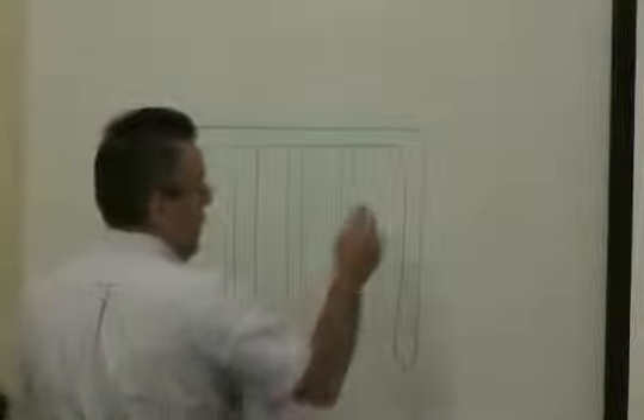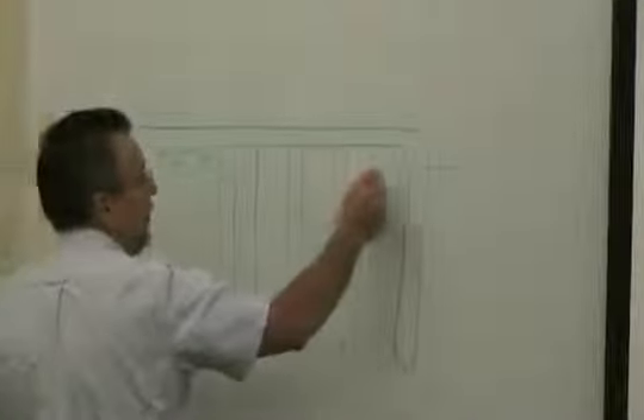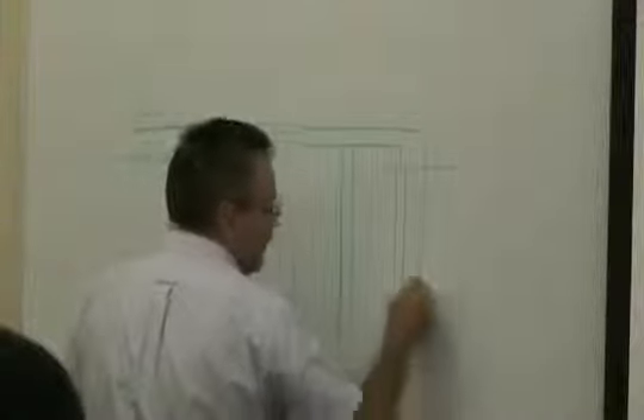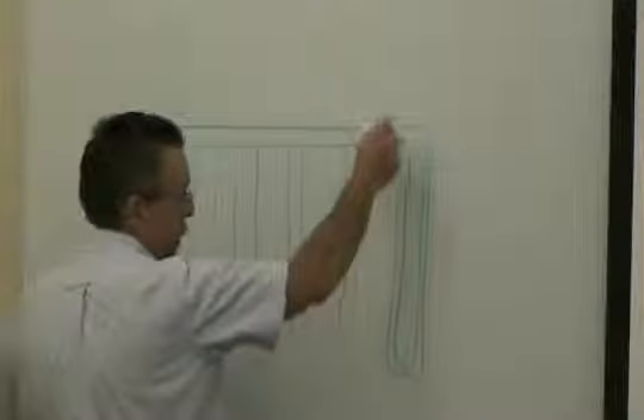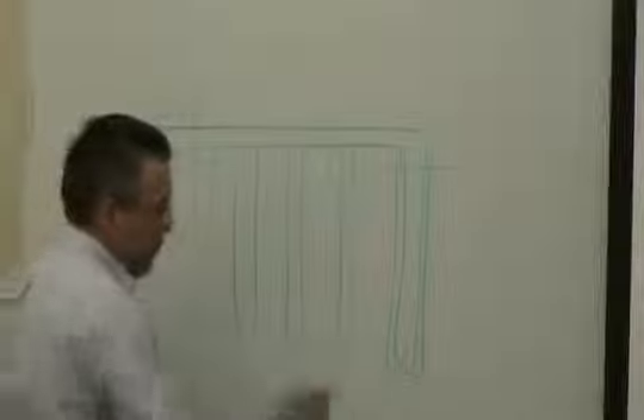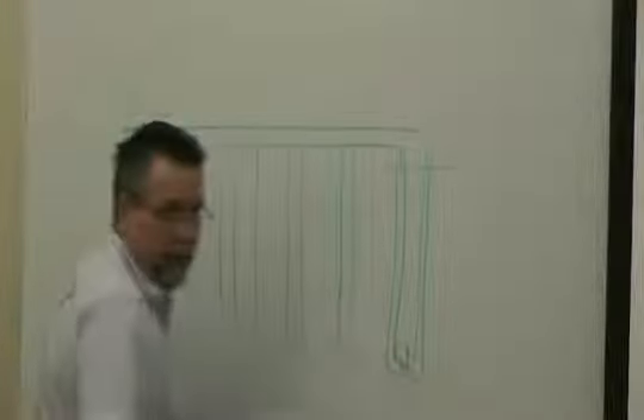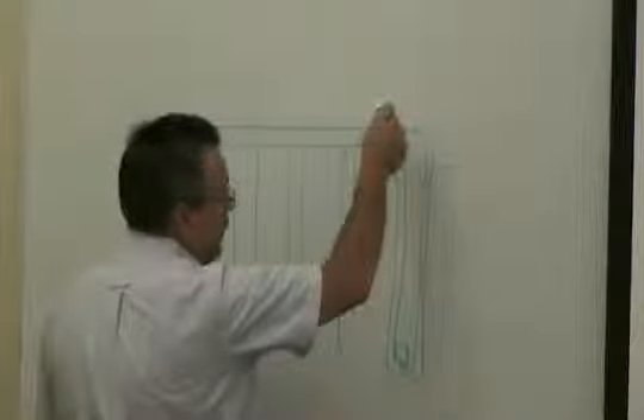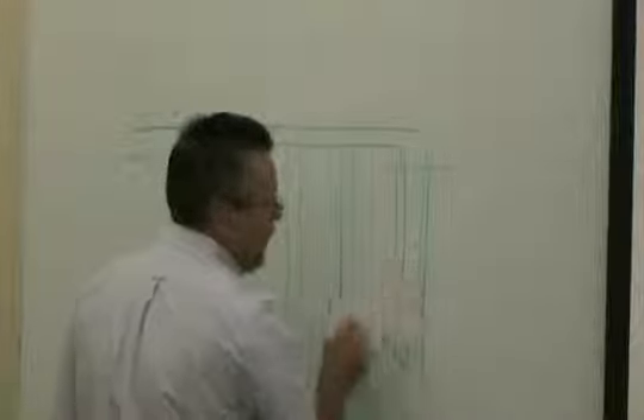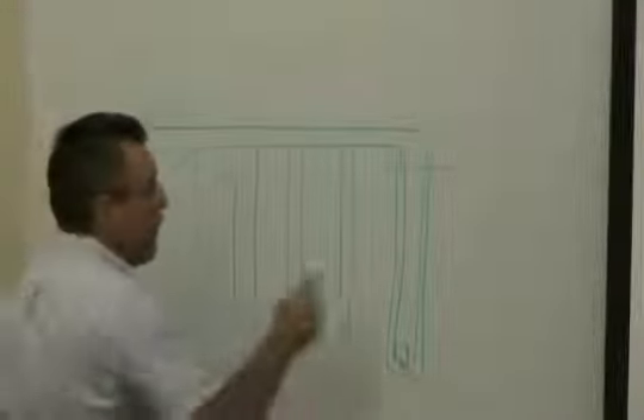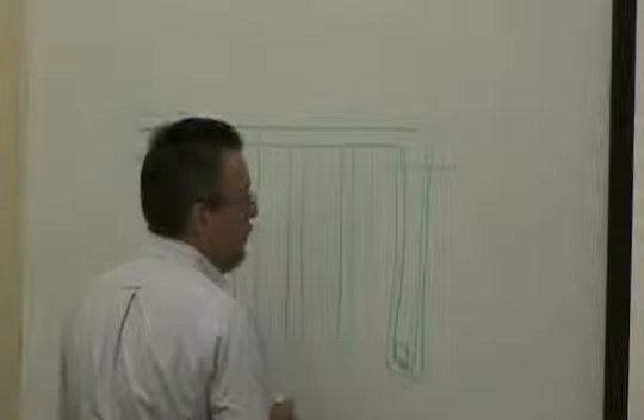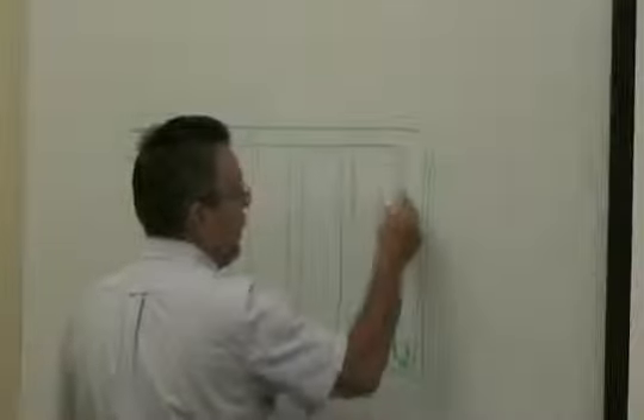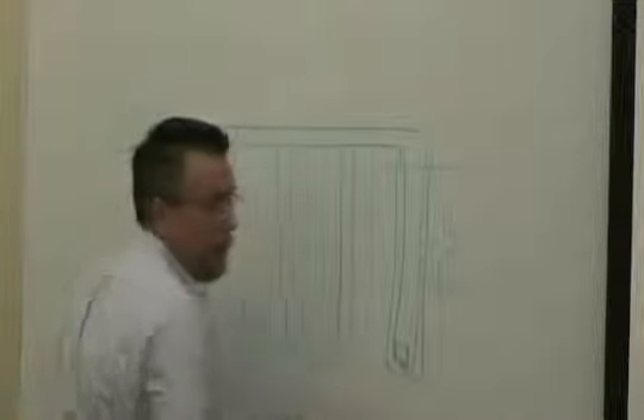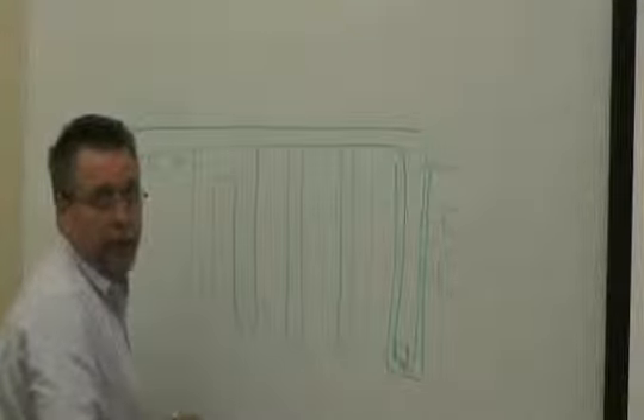Do you get water down there? Well, is that a plus or not? The plus is hitting water. So this is your well. They drill a 6-inch well, and this is a packaged roll of pipe with a typical, very close coupled U-bend connector on the bottom of it. They push your pipe down there with grout, and the grout is very important because it is your heat exchanger back to the ground. So there's a special type of grout they use, bentonite or some other type of driller's mud that they use for grout as the heat exchanger. And so generally it's a 4 to 6-inch well that's being drilled 250 to 500 foot deep.